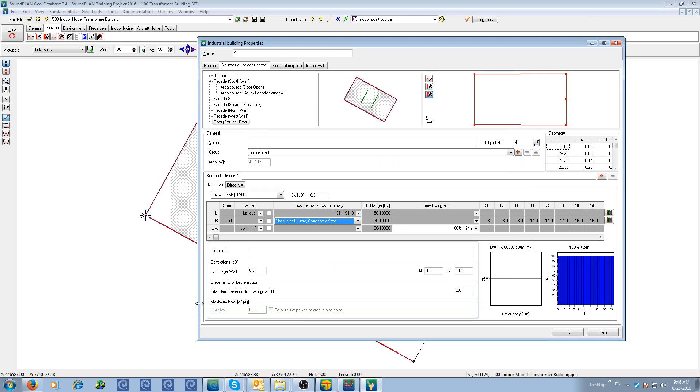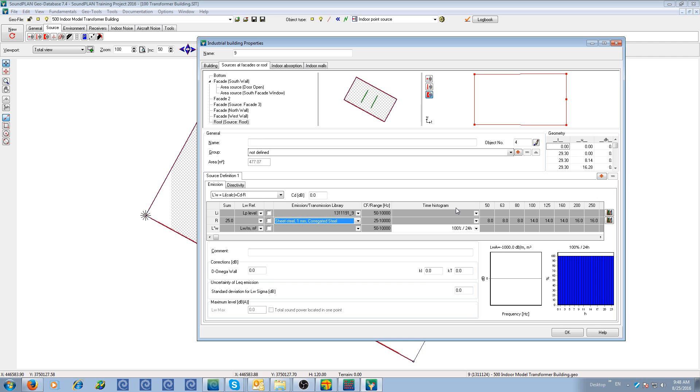That source spectrum will have source data for every hour of the day. So if you have any changes in terms of your source characterization inside the room, because it's only operating daytime or evening hours, or it's a two shift operation with a couple hours of downtime, you will have the interior noise levels for every hour of the day. With that, also the exterior noise levels for every hour of the day. So this is the combination of industrial building and exterior noise modeling and interior noise model.